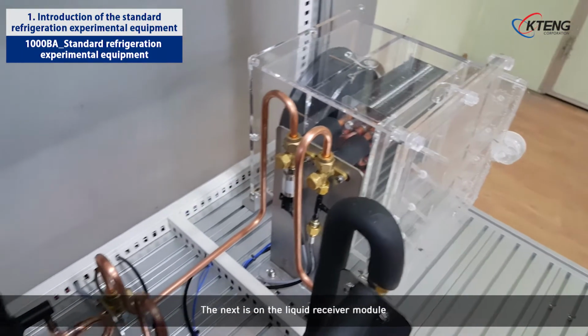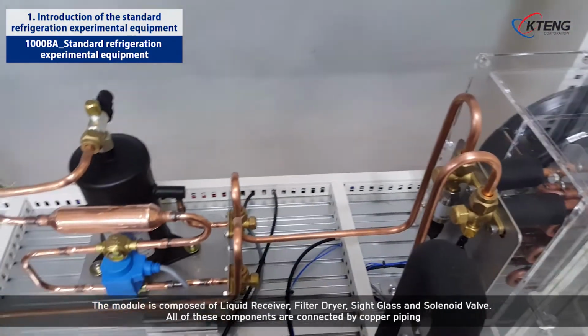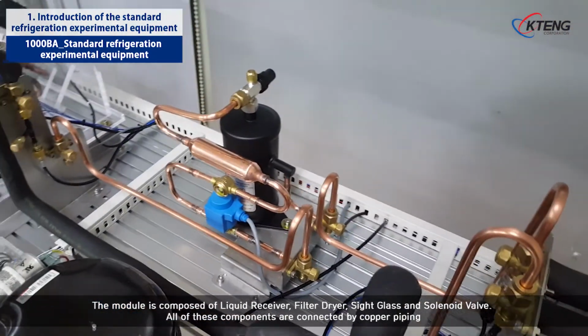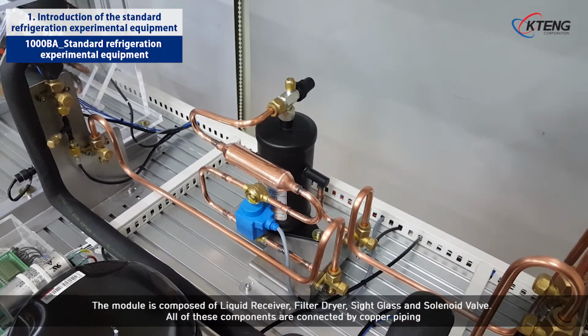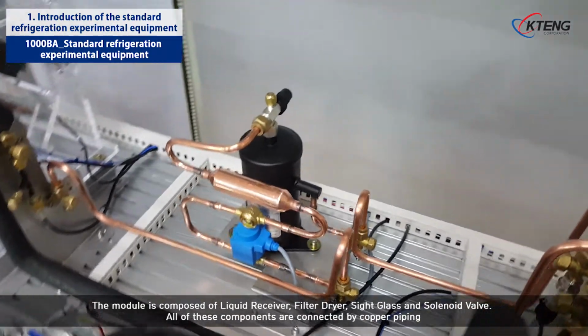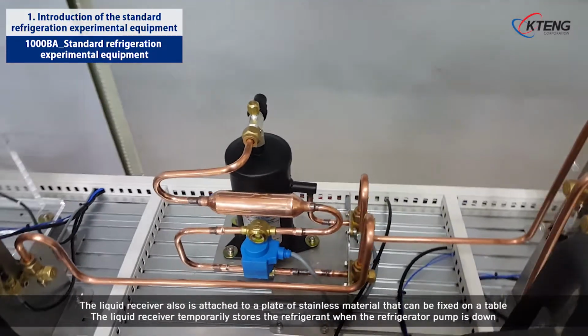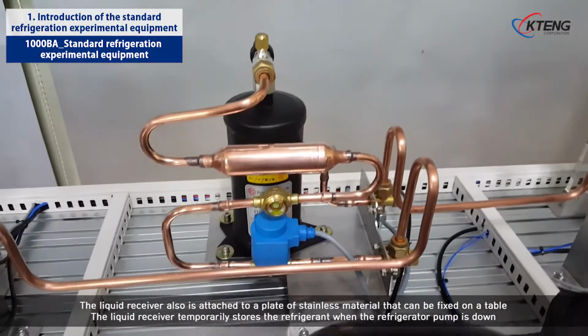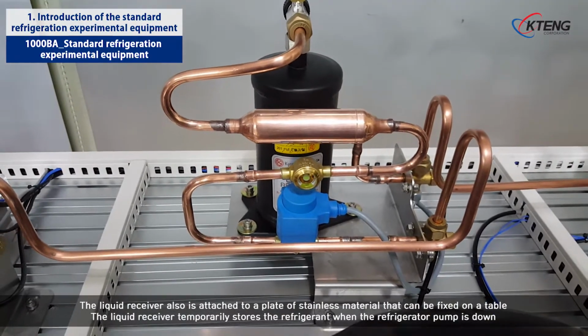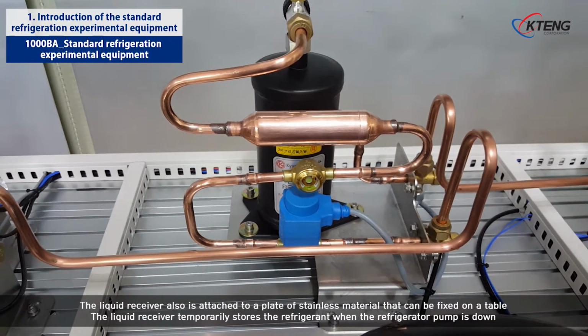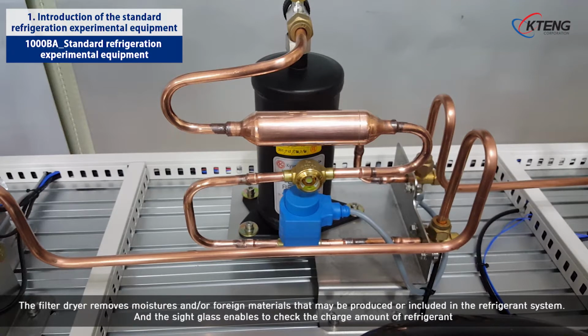The next is the liquid receiver module. The module is composed of liquid receiver, filter dryer, sight glass, and solenoid valve. All of these components are connected by copper piping. The liquid receiver also is attached to a plate of stainless material that can be fixed on a table. The liquid receiver temporarily stores the refrigerant when the refrigerator pump is down. The filter dryer removes moisture and/or foreign materials that may be produced or included in the refrigerant system, and the sight glass enables checking the charge amount of refrigerant.